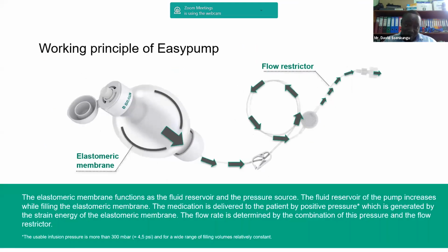If we look at the operational principle of our elastomeric pumps, the elastomeric membrane functions as the fluid reservoir and the pressure source. The fluid reservoir of the pump increases while filling the elastomeric membrane. The medication is delivered to the patient by positive pressure, which is generated by the strain energy of the elastomeric membrane. The flow rate is determined by the combination of this pressure and the flow restrictor. So that's basically the working principle of this elastomeric pump.